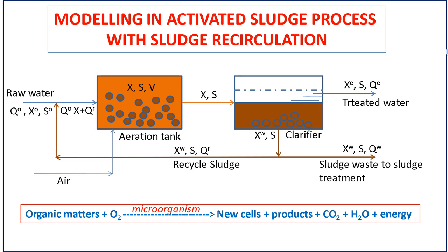The liquid mixture from the aeration tank then flows into a sedimentation tank to separate the clear liquid with substrate concentration S, and microbial sludge with concentration XE — called activated sludge. The sediment from the bottom contains high microbe concentration XW, recirculated back into the aeration tank. A portion with volumetric rate QW and sludge concentration XW is discharged to sludge treatment to prevent accumulation and adjust microbial cell residence time.